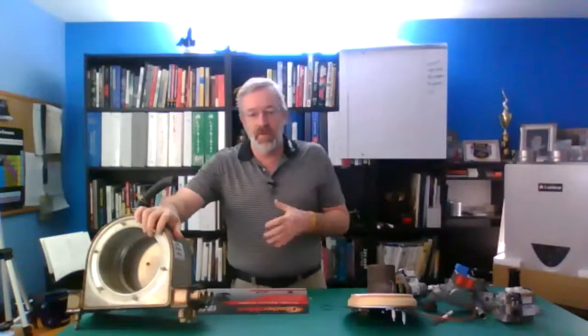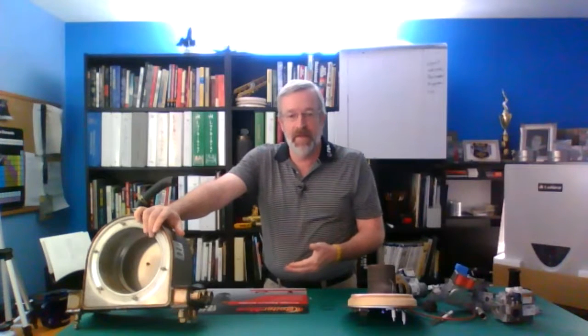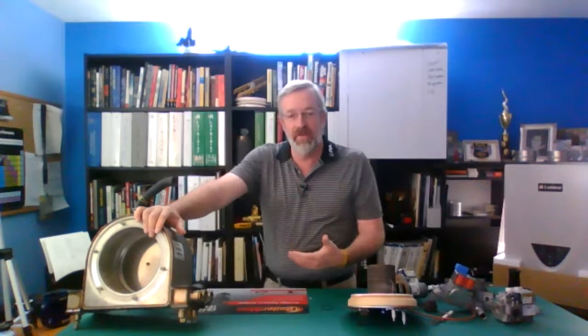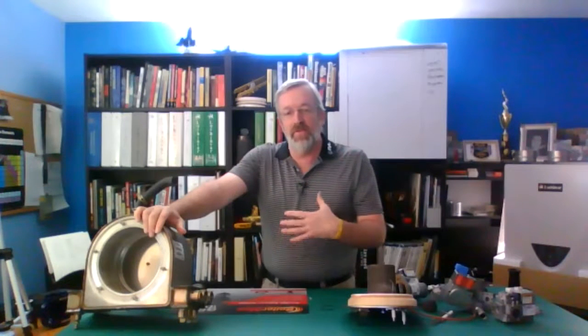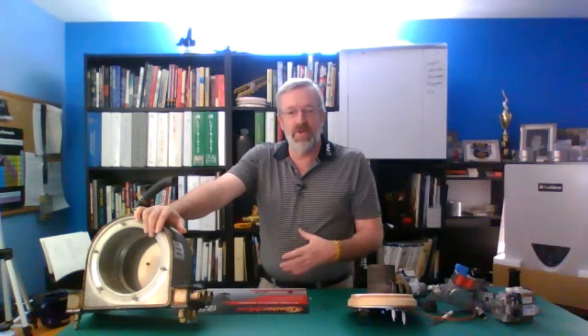So while you're there doing your PM, and we really went from how did a service call lead to a PM, but that's that air side dirty burner, dirty heat exchanger. While you're doing your PM, one of the things we want to take a look at is the cycles of our boiler. So that's going to be how many hours it runs versus how many ignition attempts. Then we want to do a little bit of math. So basically divide the run hours by the ignition attempts and let's see what we get. Generally, if I'm on this style here, no more than 6 to 10 cycles per hour of runtime, okay? When I'm on the fire tube style, really no more than 6 cycles per hour of runtime. What we want to do is let the boilers run clean, if you will, and not short cycle on and off. We want them to be efficient. We also don't want to short cycle them, which could do damage to parts and that sort of thing. So that's what we want to do.